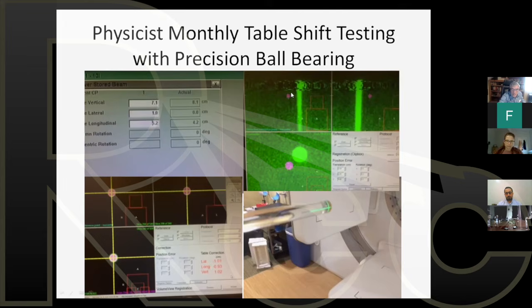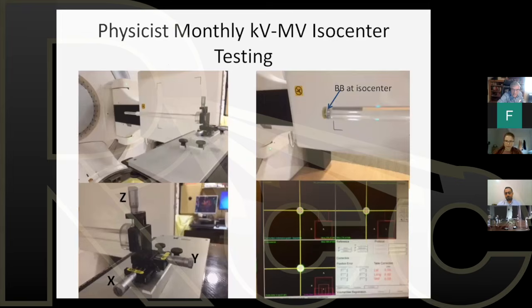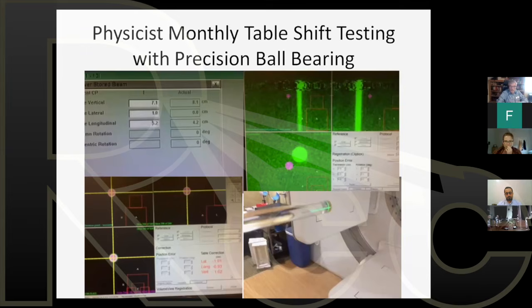So in Elekta, you would superimpose these images. You would move them with your mouse. The Elekta software calculates the offset, and then you adjust the table to that point. You go in the room, you look, and your lasers should be right on the crosshairs if everything is aligned up and working correctly.